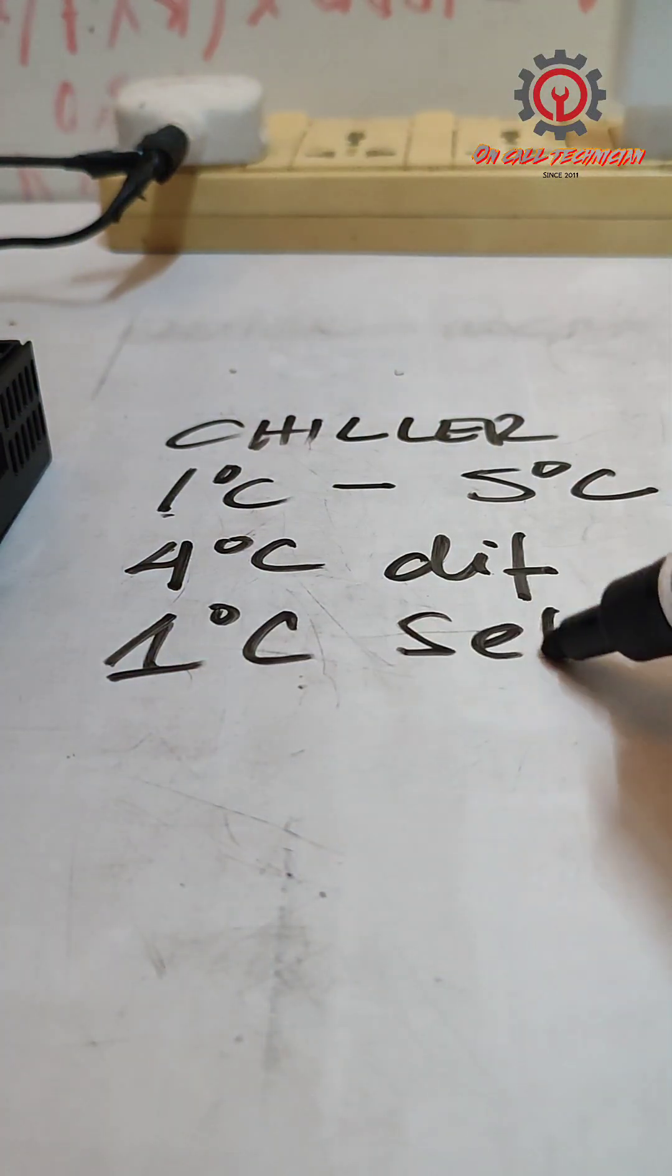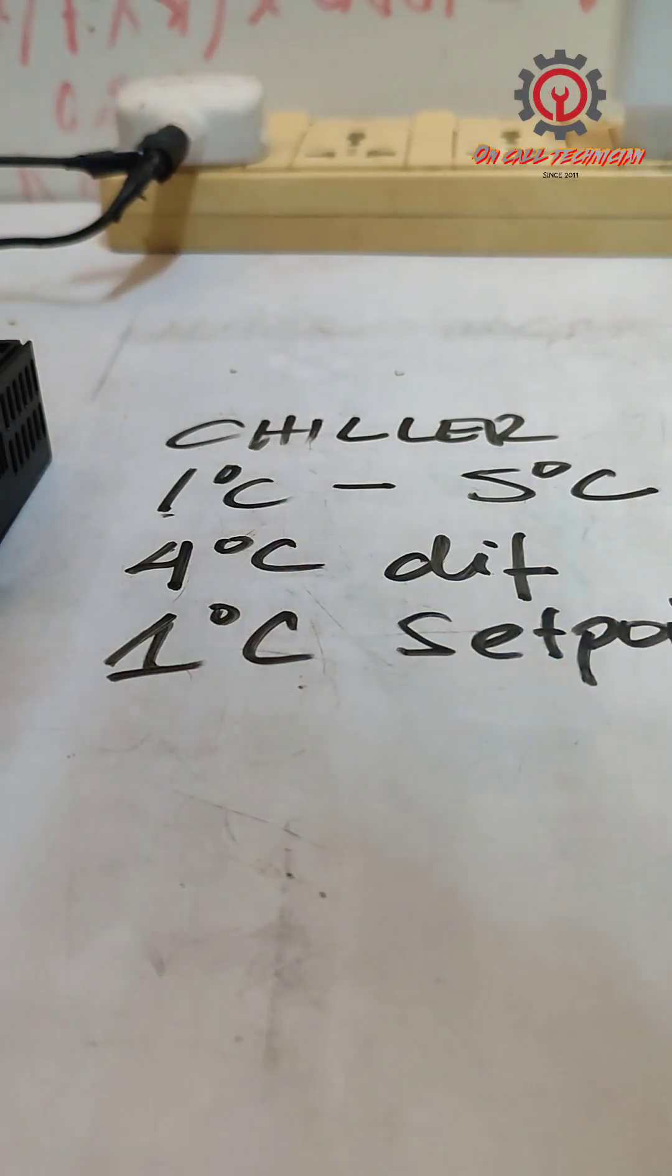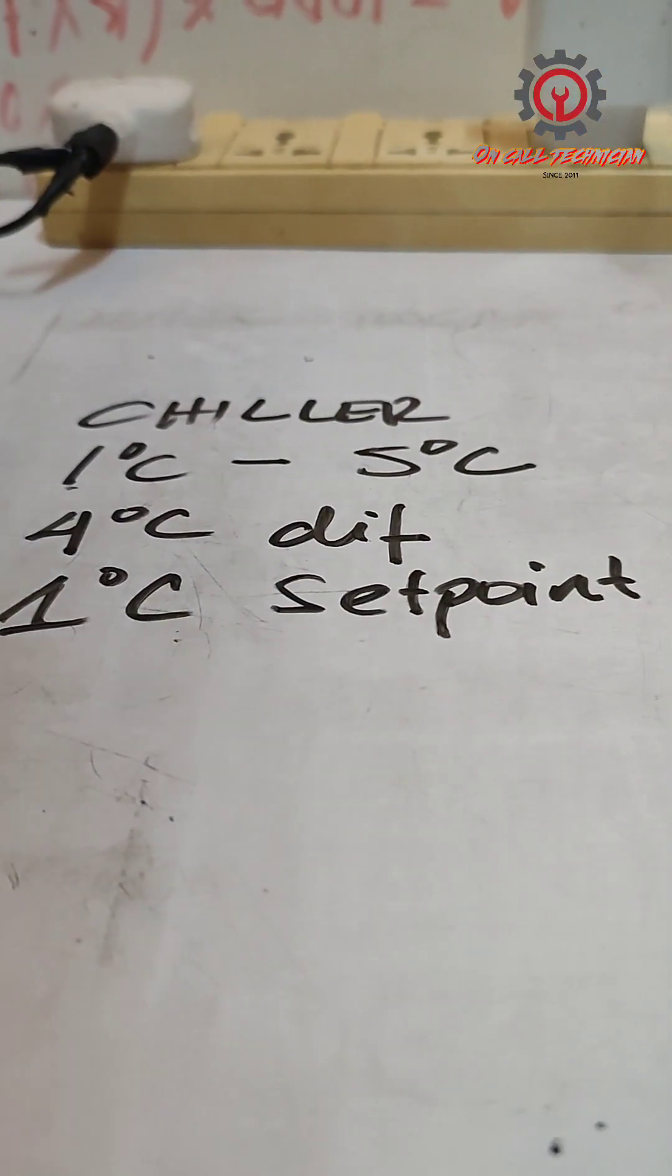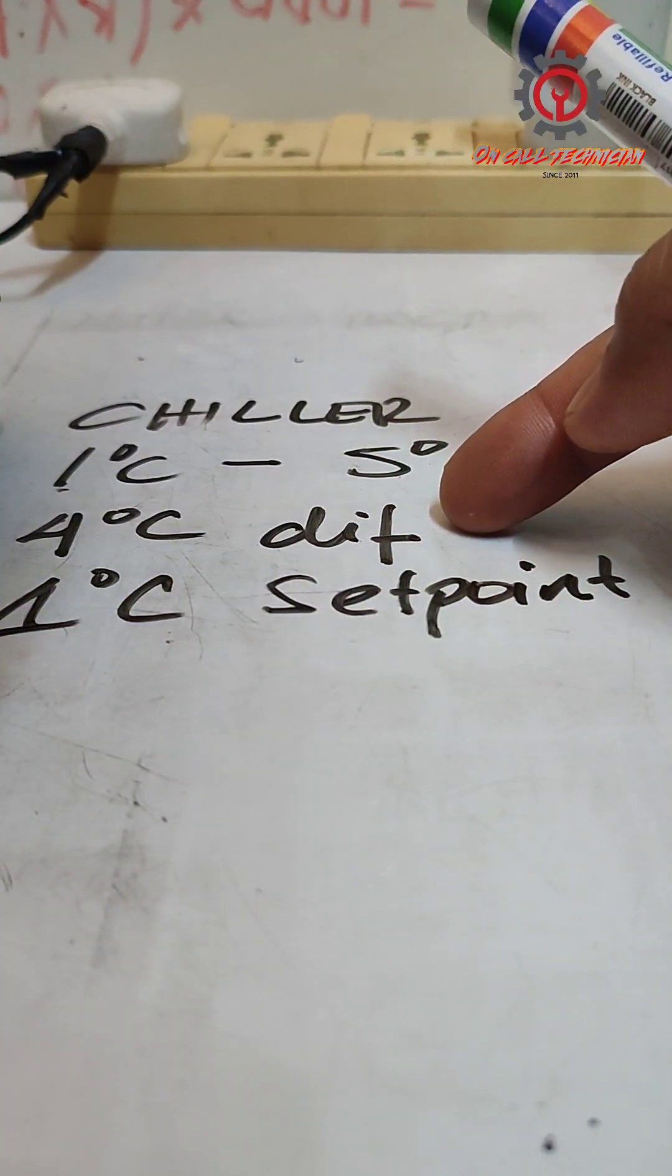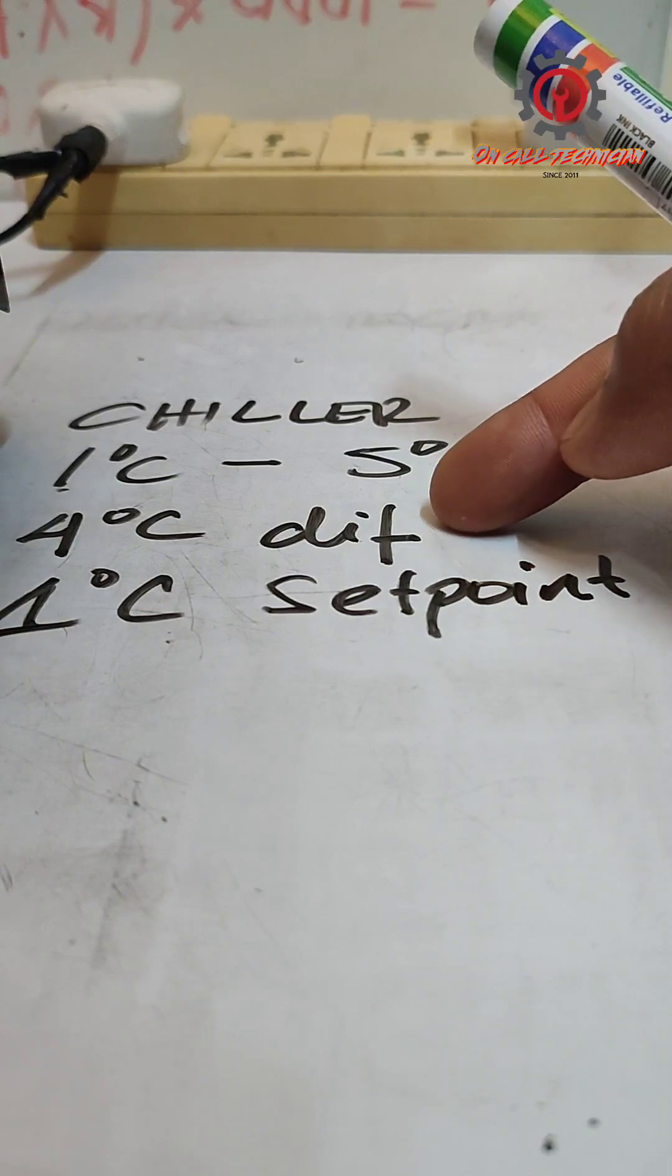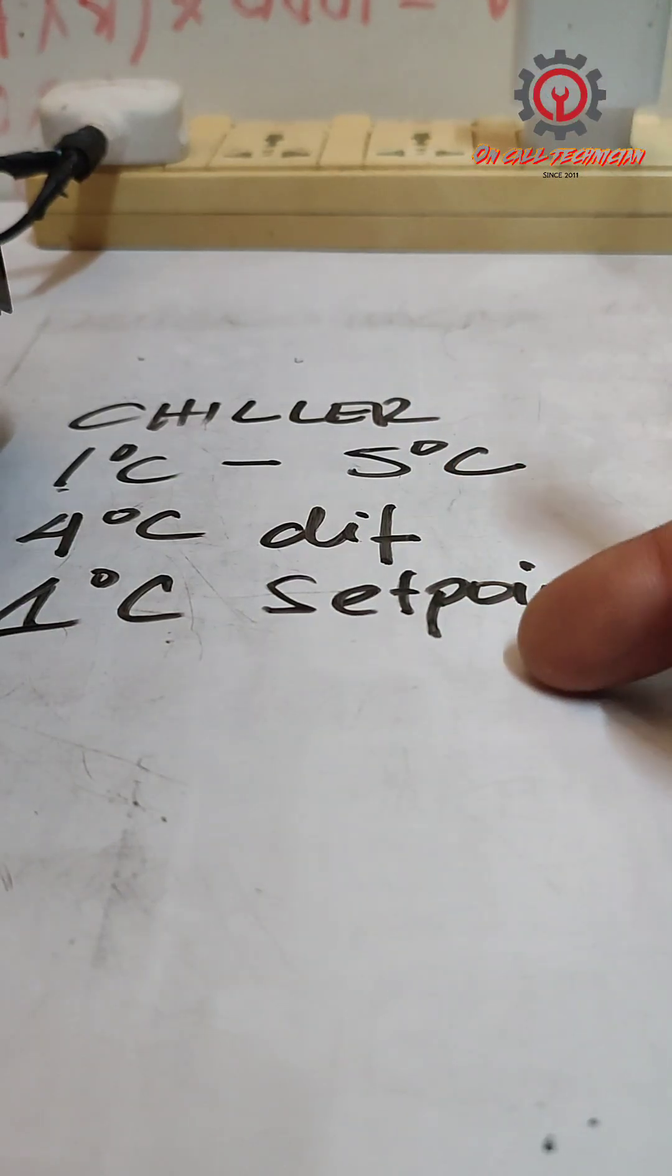While this one here is our set point. We just finished changing the set point, and now we proceed to the differential, which is the cut-in of the compressor. Set point is the cut-off of the compressor.